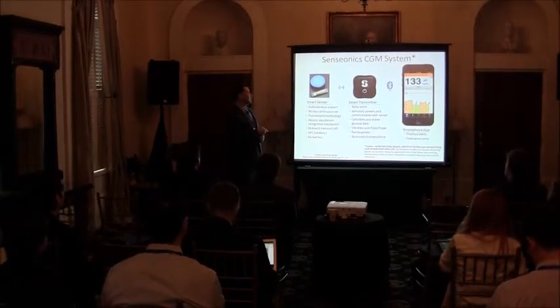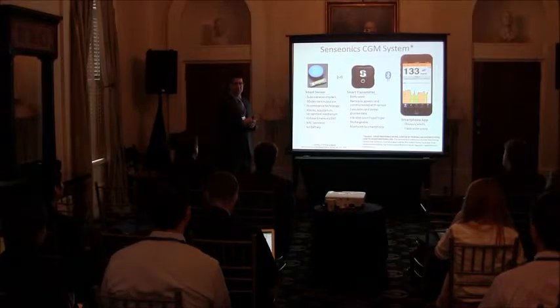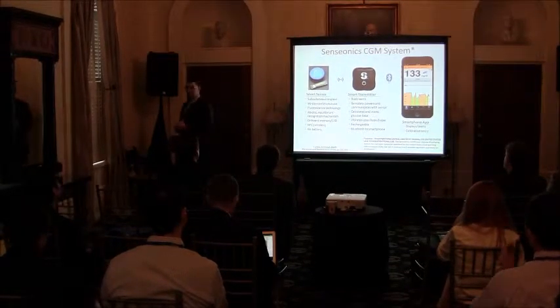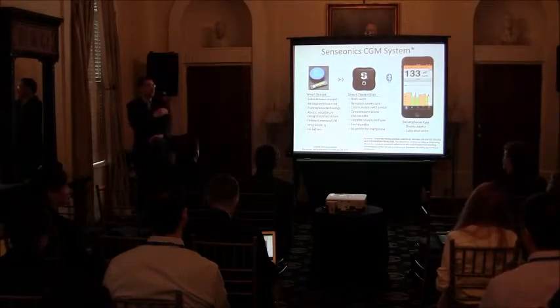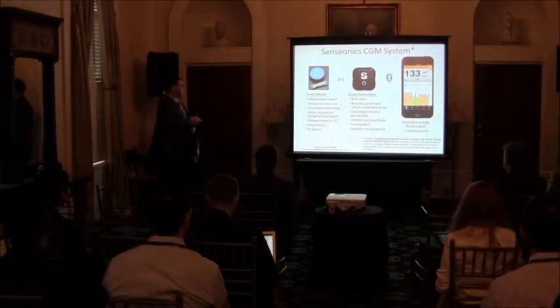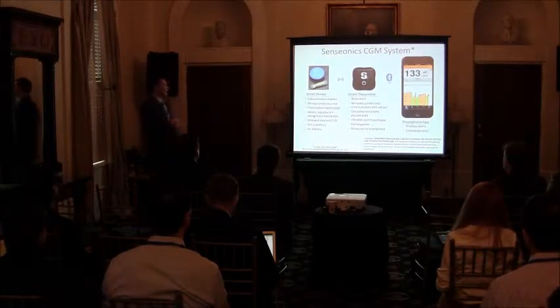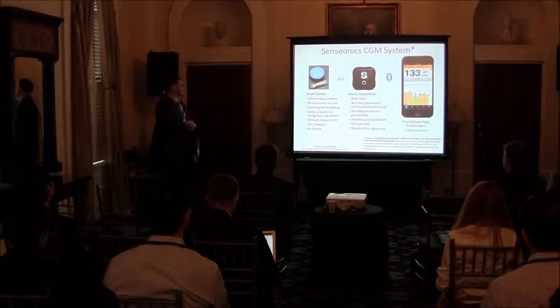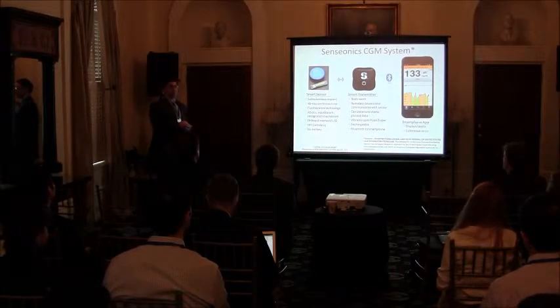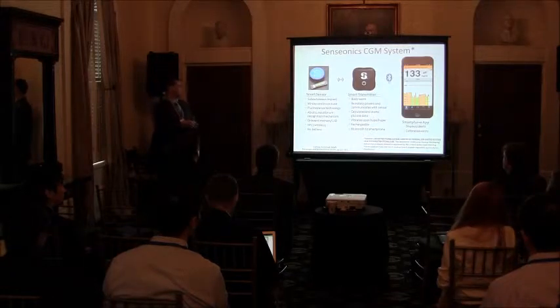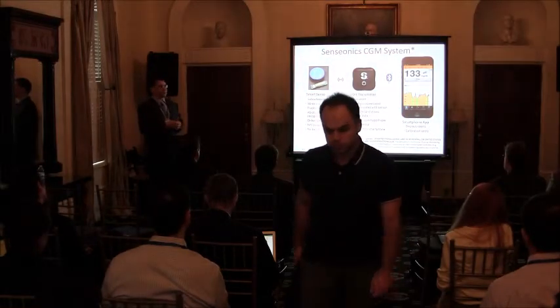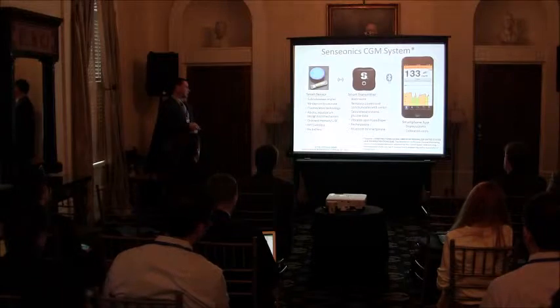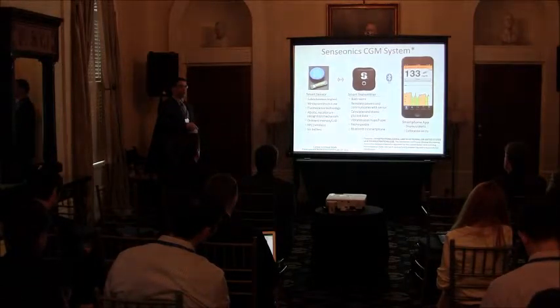So, the Senseonics CGM system. First is a smart sensor. Our sensor is actually subcutaneously implanted just under the skin in the upper arm. This is a photograph here next to an M&M, which is just kind of an icon that people can recognize. It's fluorescent based. It lasts for 3 months. It has an equilibrium recognition mechanism on the outside of the sensor. So the transducer itself is not consumed by binding to glucose. It uses NFC communication and wireless powering, and has no battery.